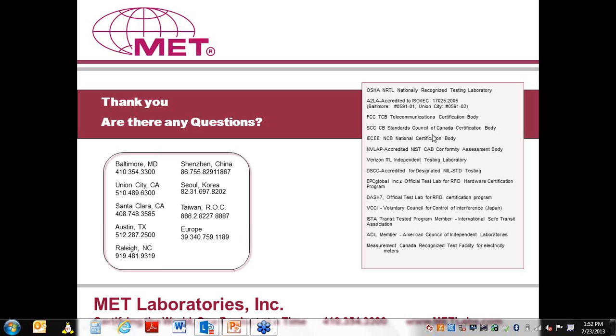The next question was, when is the real EU date of withdrawal on the second edition? That is October 1st, 2013. Now there's another question about the status of the UL version of 61010-1. For UL, you can use either second edition or third edition. However, as of January 1st, 2018, second edition will be withdrawn. At that point, anything that's still certified to second edition becomes obsolete and has to be converted. But again, this is 5 years from now.